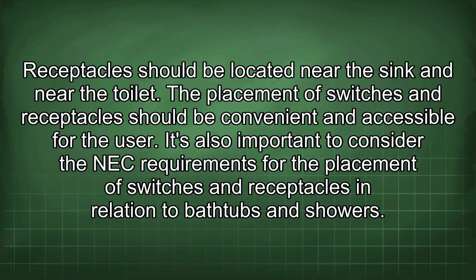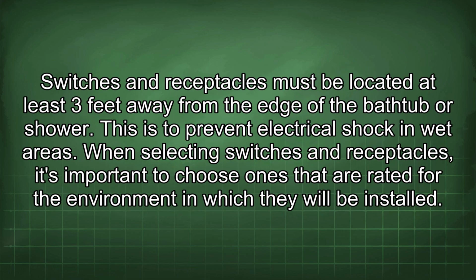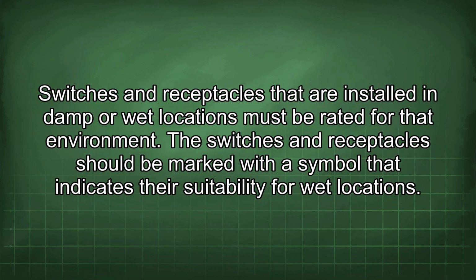It's also important to consider the NEC requirements for the placement of switches and receptacles in relation to bathtubs and showers. Switches and receptacles must be located at least 3 feet away from the edge of the bathtub or shower. This is to prevent electrical shock in wet areas. When selecting switches and receptacles, it's important to choose ones that are rated for the environment in which they will be installed. Switches and receptacles that are installed in damp or wet locations must be rated for that environment. The switches and receptacles should be marked with a symbol that indicates their suitability for wet locations.